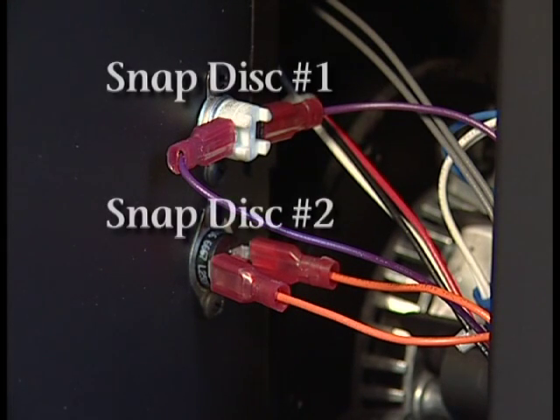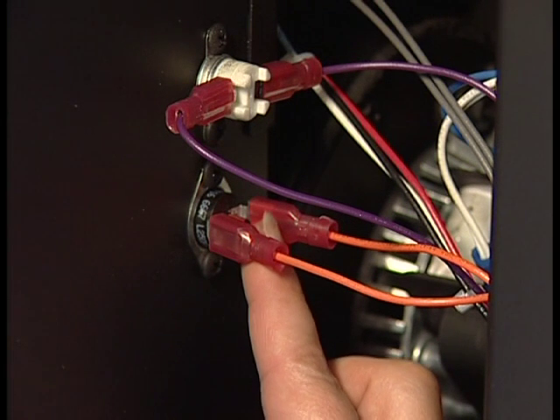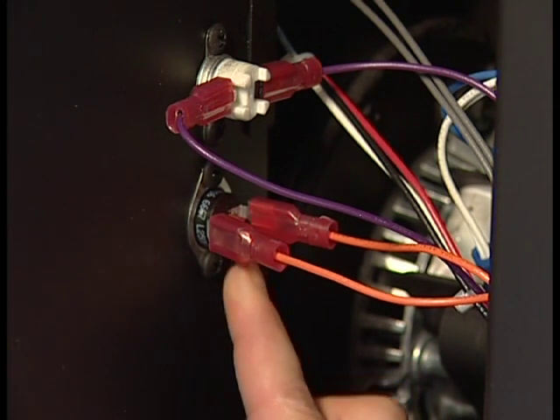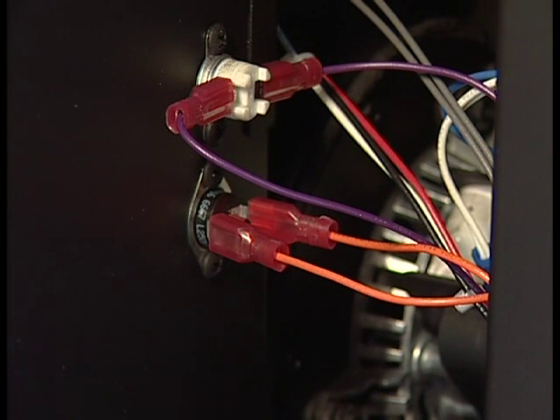Check the number 2 snap disc. This disc will turn the feed motor off if the unit gets too hot. Check the number 1 snap disc. This sensor will turn on the convection blower when it gets hot. If the number 1 snap disc failed on the previous cycle, the convection blower would not have come on and the number 2 snap disc would have tripped.